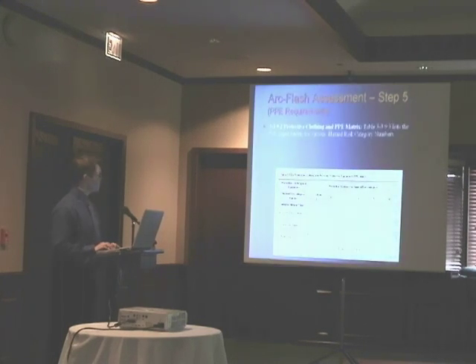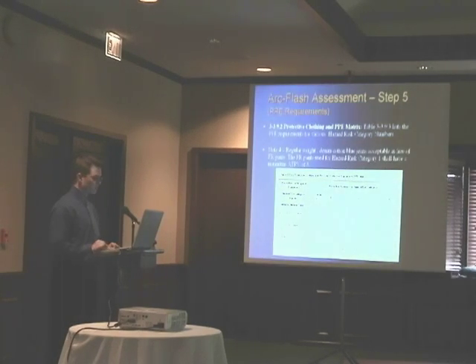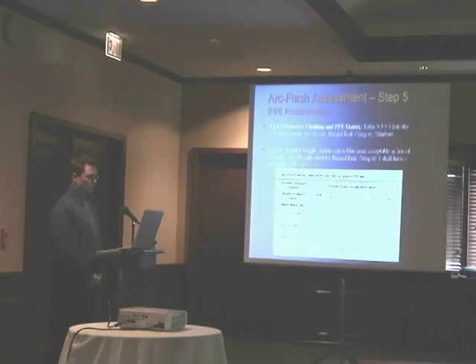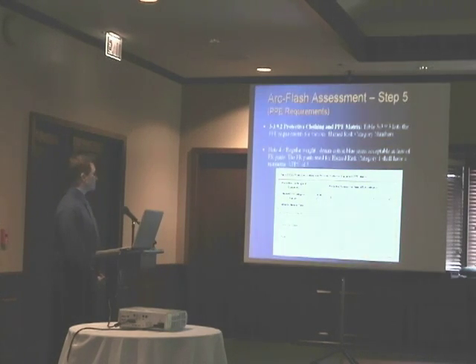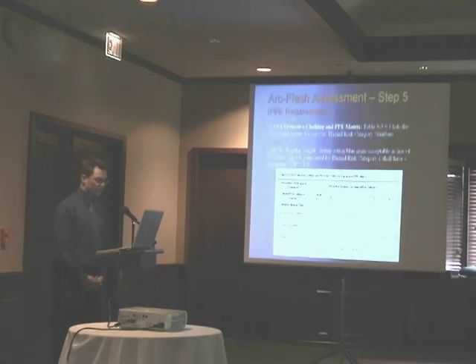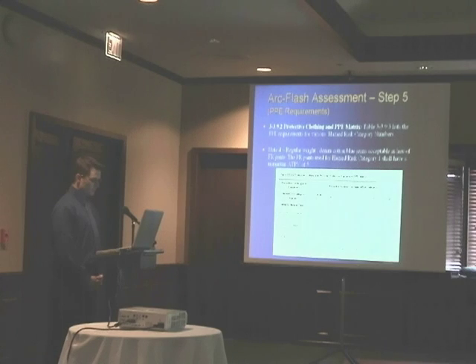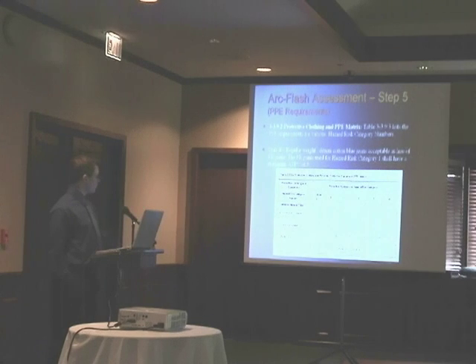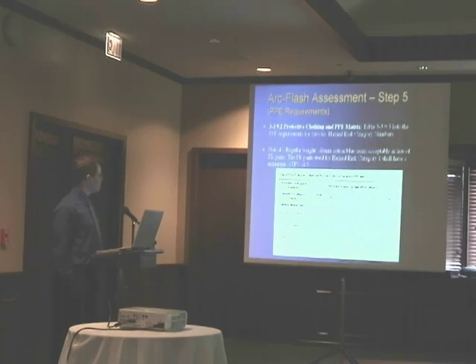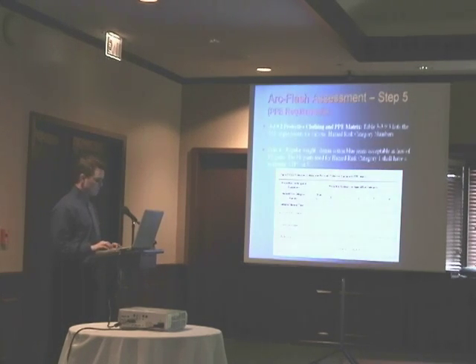Here are your PPE requirements. This is listing for the different hazard and risk category numbers. Now, note 4 on the right, regular weight cotton or denim cotton jeans are acceptable in lieu of FR flame resistant pants. The flame resistant pants used for the hazard risk category 1 should have a minimum ATPV of 5. This is just showing you what you will need for different categories from 0 to 4 for your PPE requirements. I'm going to go over this a little more in a second.